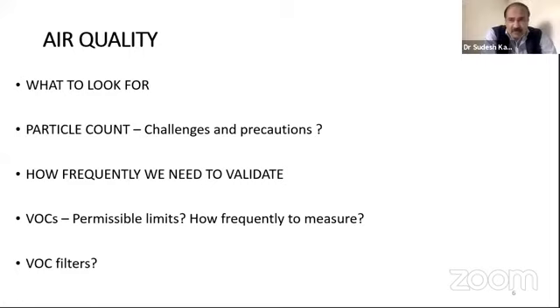As per the ICMR guidelines, you have to have an air handling unit, and the AC should come through the AHU. Many centers also have CODA towers, but it's recommended to have air handling units, especially in a place like Mumbai where we work with small spaces—the air handling unit sits on the ceiling and doesn't take up space like CODA towers do. Sometimes CODA towers can remove more particles, but a central air handling unit is more than sufficient.